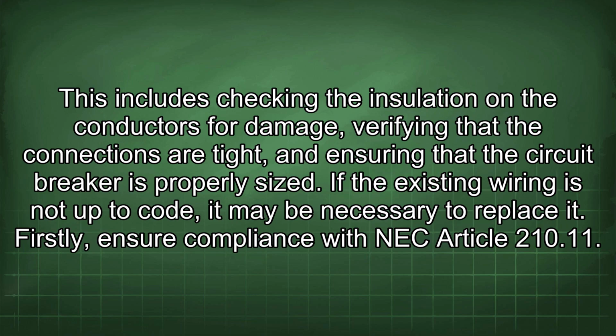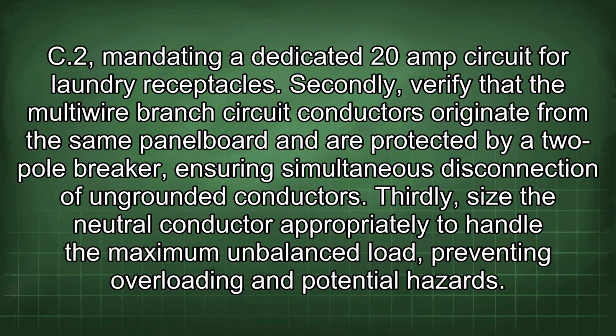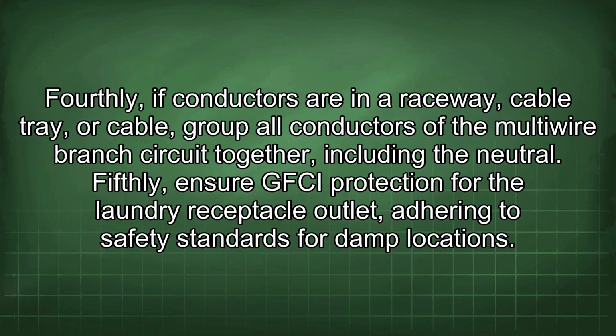Firstly, ensure compliance with NEC Article 210.11(C)(2), mandating a dedicated 20 amp circuit for laundry receptacles. Secondly, verify that the multiwire branch circuit conductors originate from the same panel board and are protected by a 2-pole breaker, ensuring simultaneous disconnection of ungrounded conductors. Thirdly, size the neutral conductor appropriately to handle the maximum unbalanced load, preventing overloading and potential hazards. Fourthly, if conductors are in a raceway, cable tray, or cable, group all conductors of the multiwire branch circuit together, including the neutral. Fifthly, ensure GFCI protection for the laundry receptacle outlet, adhering to safety standards for damp locations.